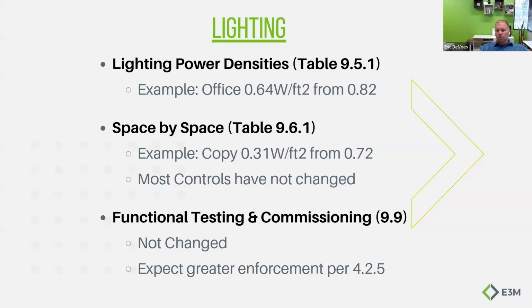The last thing I'll mention on this is functional performance testing has not actually changed for lighting. That was the only thing under the 2013 code that Michigan didn't amend out. It was supposed to be tested for lighting controls and lighting levels, but most jurisdictions were not enforcing that. They had a hard time saying your electrical contractor on his lighting was the only thing we're going to test, so they've kind of let this slide for the last 6 years. There are jurisdictions, Holland Township for example, that would request this, but most weren't. What I'm hearing from code officials now is they're saying we're going to enforce this. If we're requiring HVAC, envelope, and power systems to be tested, we're going to require that the lighting gets tested as well.